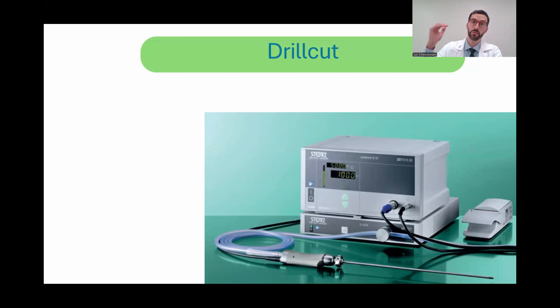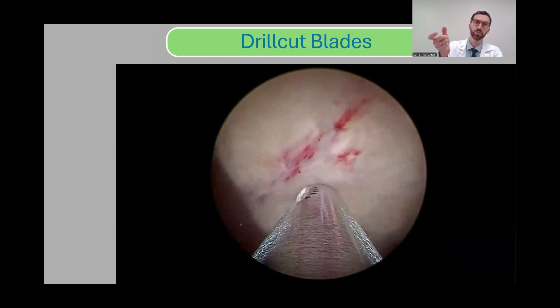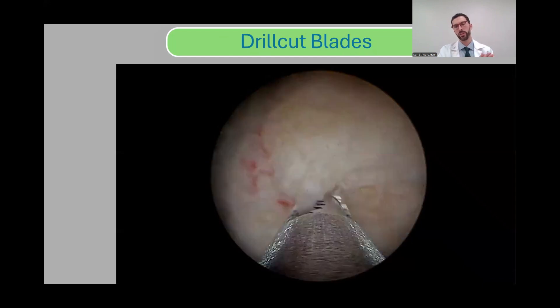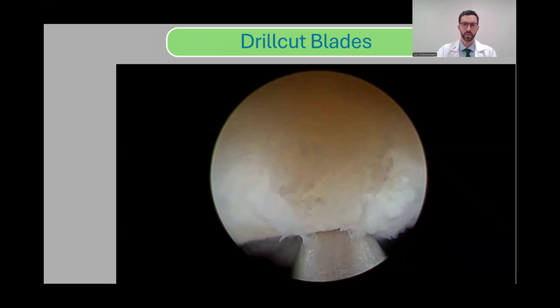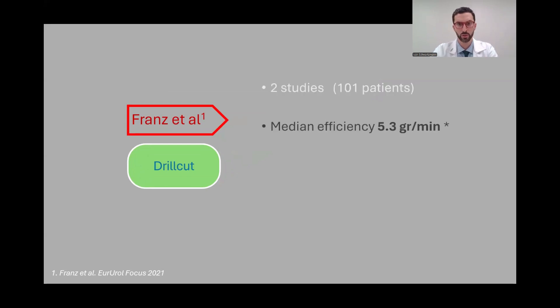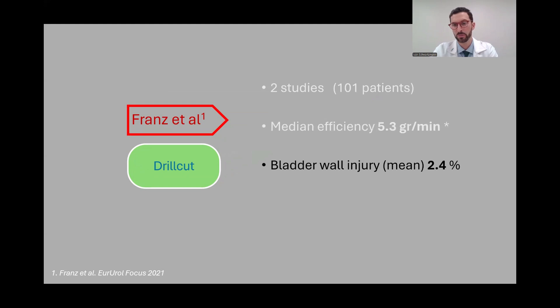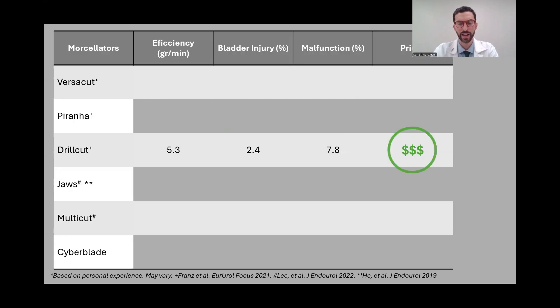The third morselator, and one of the first new morselators, is the Drillcut, developed by Karl Storz — rough inside and outside. It is also an oscillating morselator with a vacuum generator, very similar in functioning to the Piranha. The available evidence drops dramatically here: only two studies are available. The median efficiency is very similar to the Piranha. The bladder wall injury rate is also similar at about 2.4%, but the device malfunction rate stands out at almost 8% — very high. It's also on the higher end of the price range.